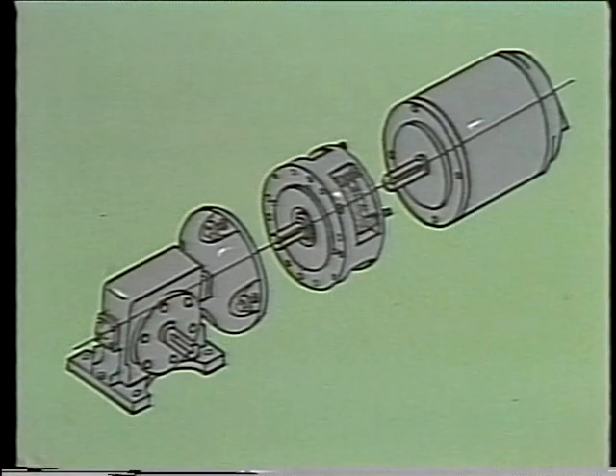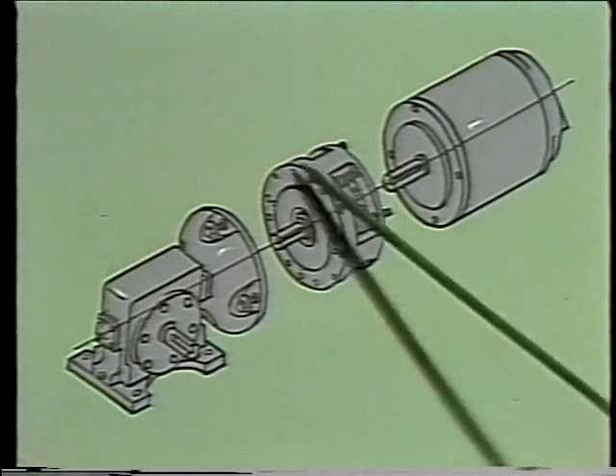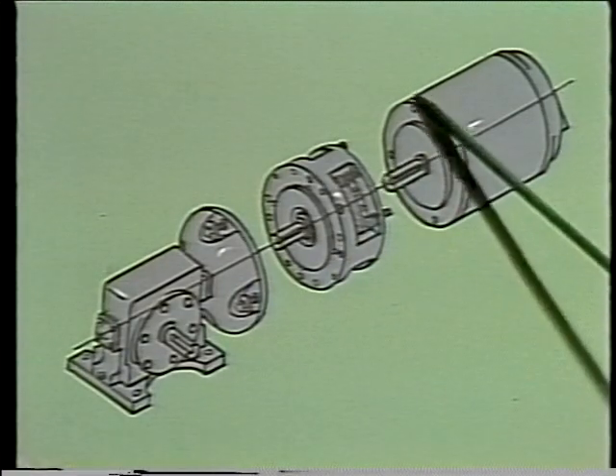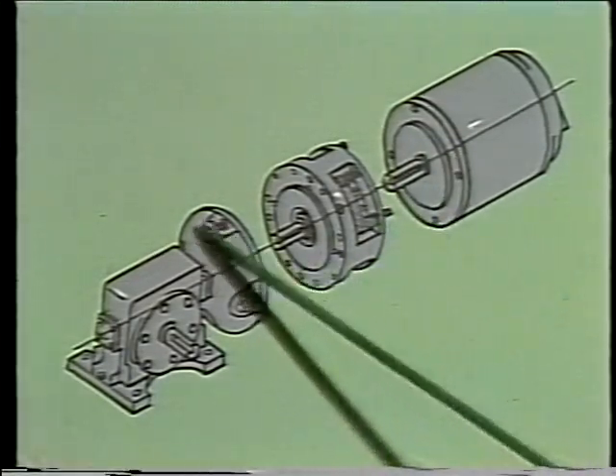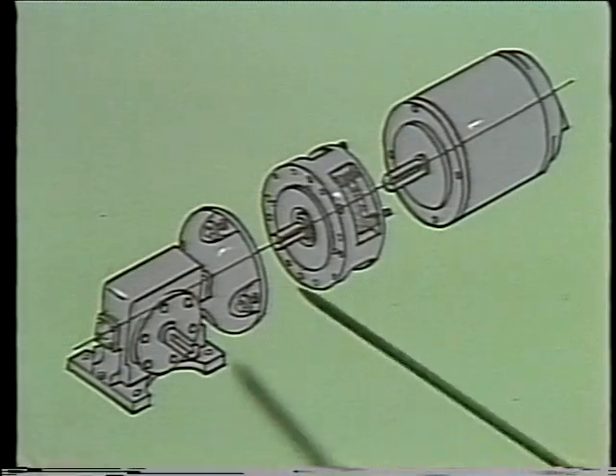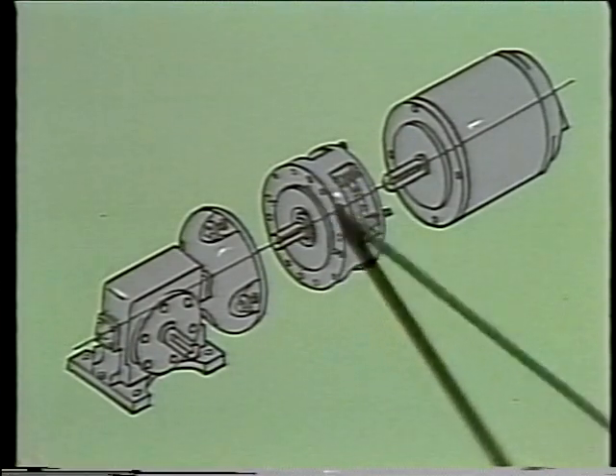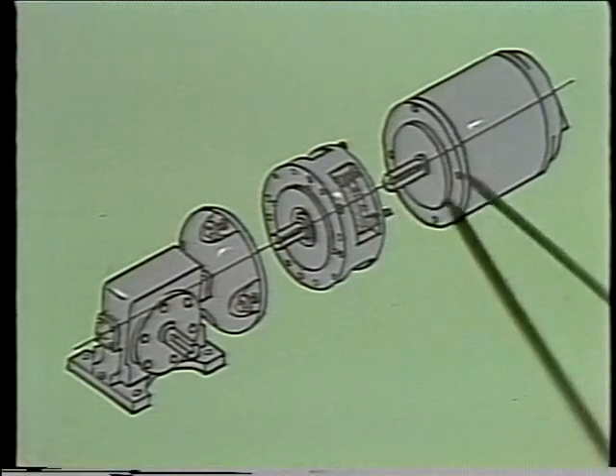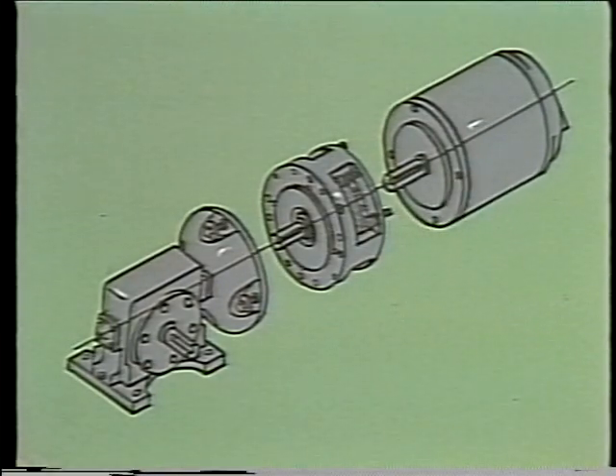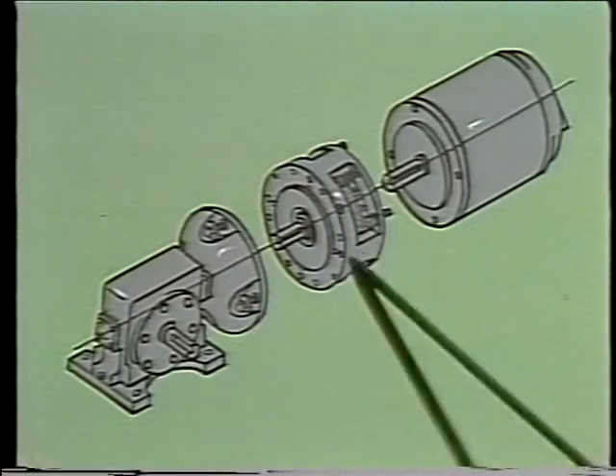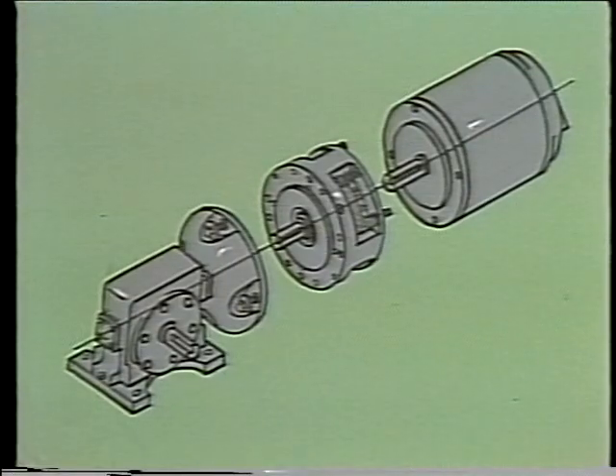In recent years, standard C-face clutch modules have been used in conjunction with standard C-face motors like this, which allows us to build up a system with a clutch or a brake by mounting it directly on the motor. Now, this greatly simplifies assembly of a unit in the field from stock parts. These are supplied as clutch units or brake units or a combination brake and clutch. They're available either air or electrically actuated. And for a complete discussion of C-face motors, see our motor tapes or our reducer tape.